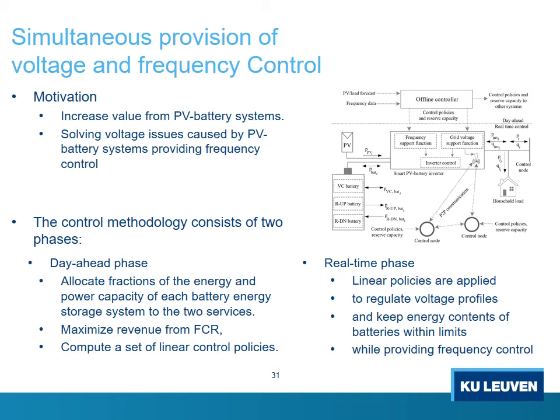The frequency support function calculates the power of the frequency containment reserve and also applies the energy management policy to maintain the energy content of the battery within limits while providing frequency control. Another thing in the thesis, which is novel, is that we divide each battery into 3 virtual batteries: one related to voltage control that controls the voltage together with the inverter reactive power, one that participates in upward frequency regulation, and one that participates in downward frequency regulation.